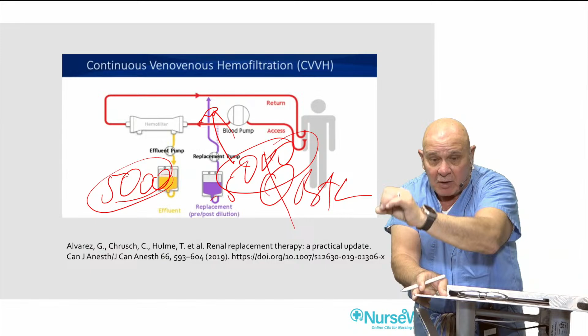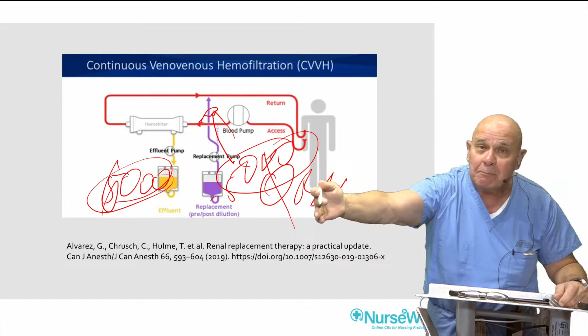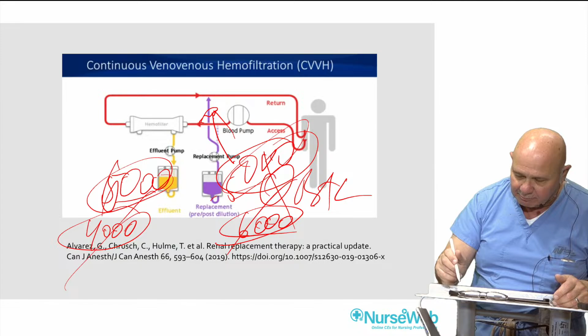but you can increase the patient fluid removal rate. So I could have 6 liters of ultrafiltrate over some period of time, we'll say 24 hours, to remove a liter from the patient, but only give them back 5 liters. I can never take 4 liters from the patient and give them back 6 liters. That's not possible to do. Impossible.